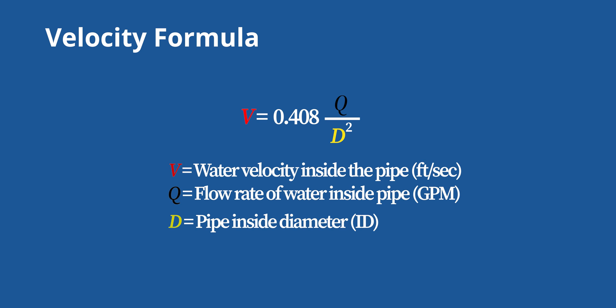Fortunately, we have already gathered this information — we just need to convert our gallons per hour into gallons per minute by dividing by 60. For the pipe inside diameter, you don't want to enter the nominal size, which is one half inch expressed as a fraction. You want to enter the actual inside diameter. The most common size of poly tubing we're using is 0.600 inches inside diameter.